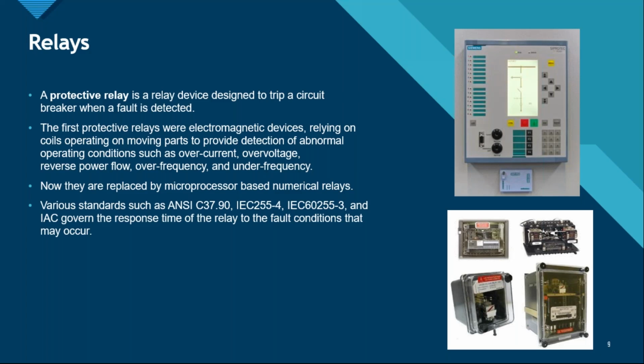Various standards are there for the relays as well. It can be ANSI standards, IEC standards, and IAC standards. They govern the response time of the relay to the fault conditions that may occur. Depending on the fault condition, depending on the rating of the current, higher the rating, bigger the disaster. So depending on the rating, depending on your requirement, system requirement, it can be customized. The electronic relays can be programmed as such to detect the fault and trip in the minimum amount of time, basically in mere milliseconds. It can give a tripping command to the circuit breaker.